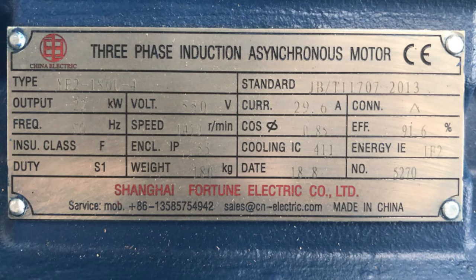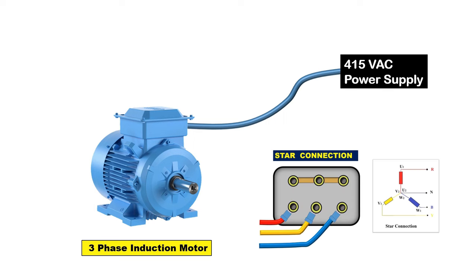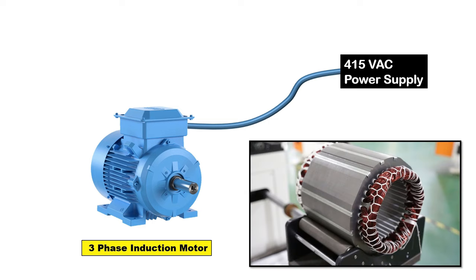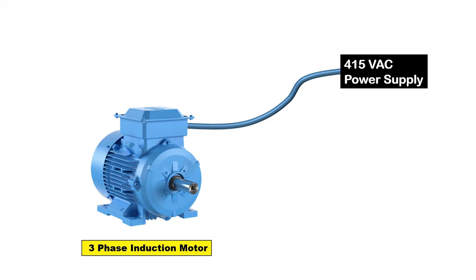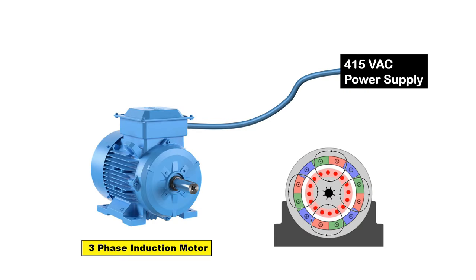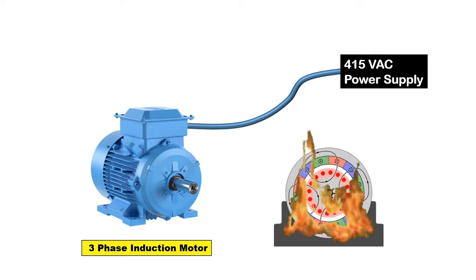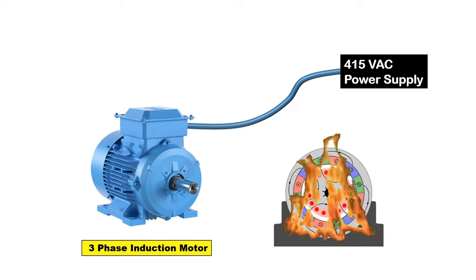Before ending this video, I want to tell you one more thing. If you see the data plate of the motor, then on the data plate, the symbol of star and delta is there. If on the data plate only star symbol is there and it is told you have to connect motor winding in star, then please don't connect motor in delta. Because the insulation of the motor winding is designed according to star connection. If you connect motor winding in delta and high current flows, then insulation of motor will become weak and even your motor may burn out. So be careful about this point.